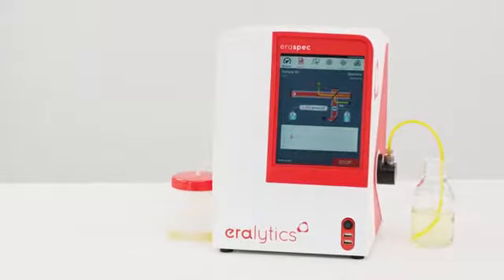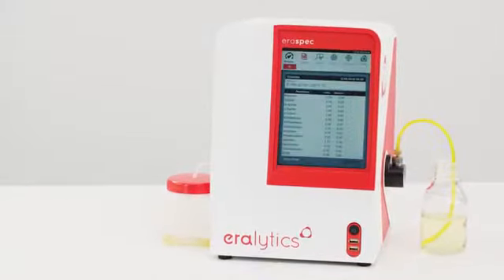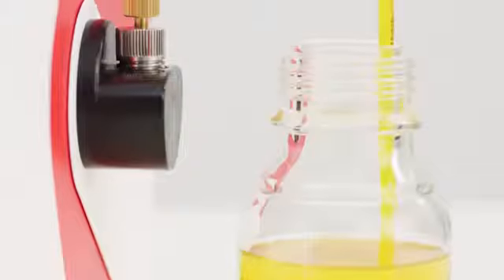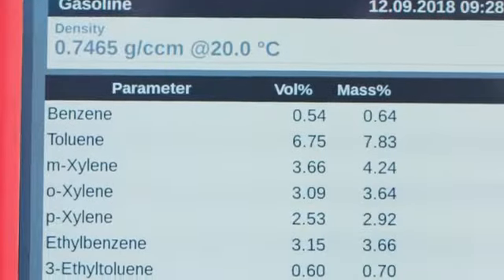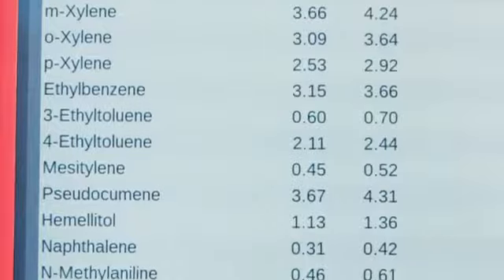Gasoline, diesel, jet fuel and biofuels are measured within 60 seconds. The portable multi-fuel analyzer eraspec measures a mid-infrared spectrum and delivers highly accurate results for the most important fuel parameters such as benzene, oxygenates and biofuel content according to international standards.